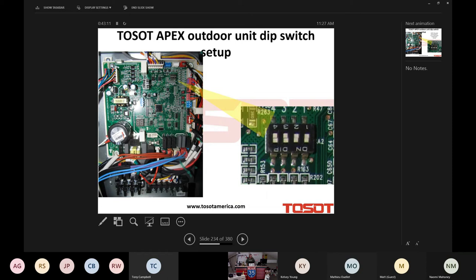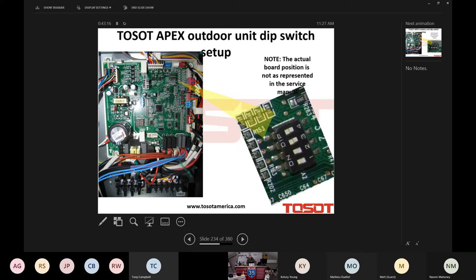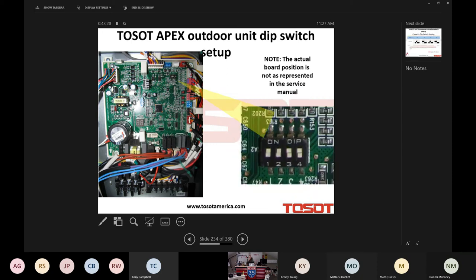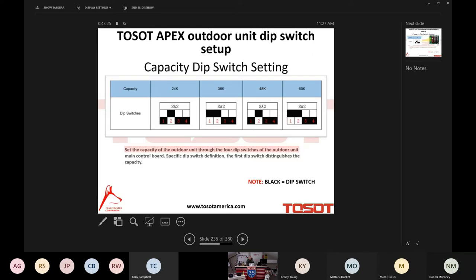All right. Dip switch setup of the outdoor unit. Let's get through that. Pretty simple. Once again, you can see the board is upside down. So just for the ease of describing it to you, I'm going to rotate that 180 degrees. So once again, guys, if you look at this picture quickly and you're like me, you start looking for 4 sets of dip switches. There are not 4 sets of dip switches. There is just the 1 set, and it is right here, right there on the board. So that's all you're looking for.